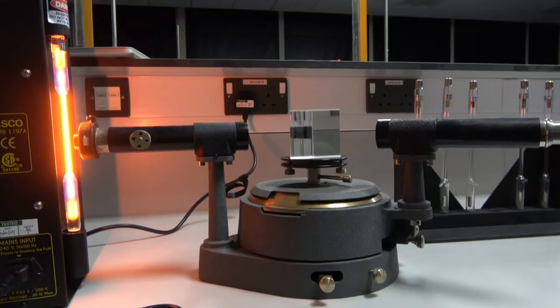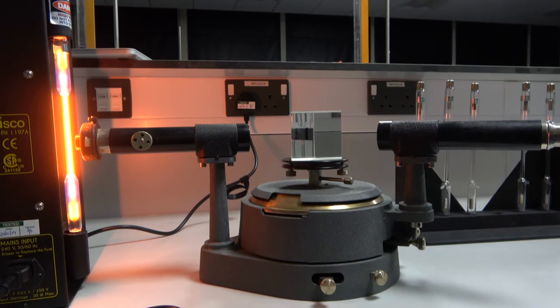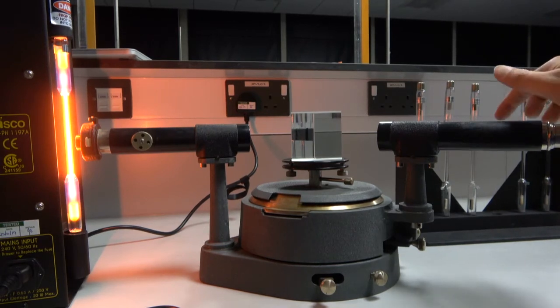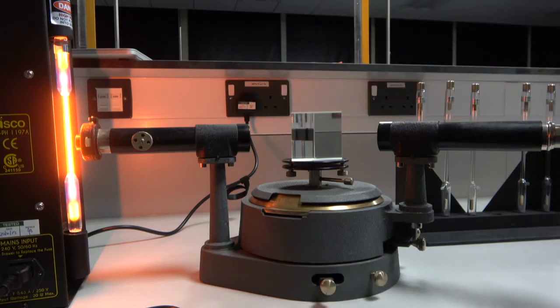So finally I just need to focus this which I'm going to do using the focusing knob on the other side of the telescope that I've already shown you and the one on the collimator. So we just look through, adjust one until the lines are sharp as they can be, then adjust the other and repeat this until we've got the sharpest possible lines we can see.